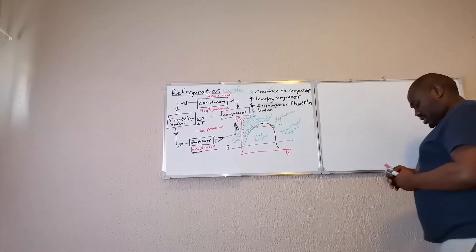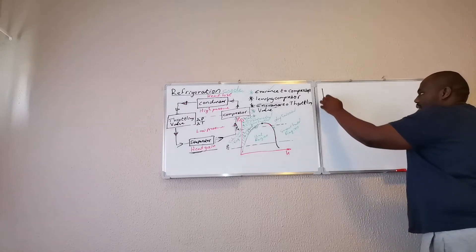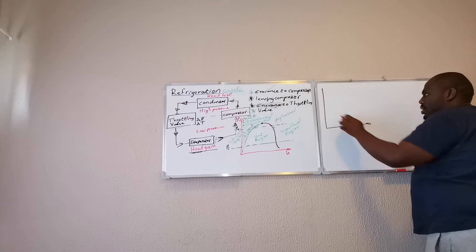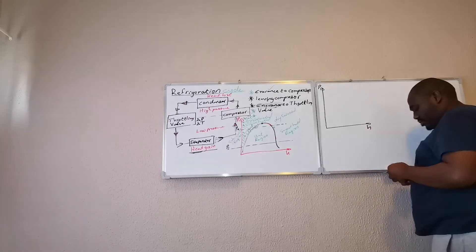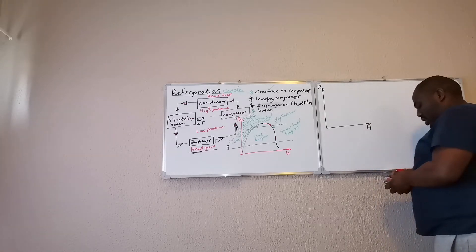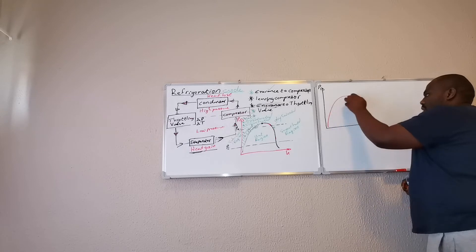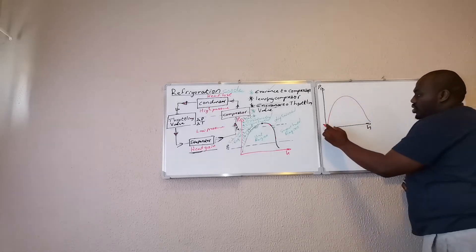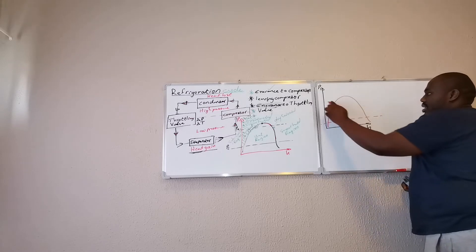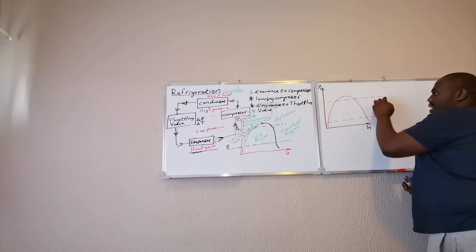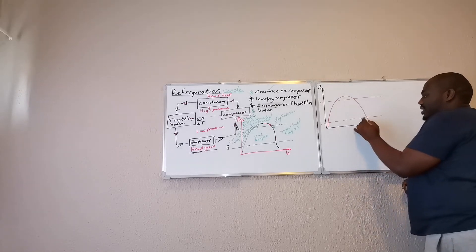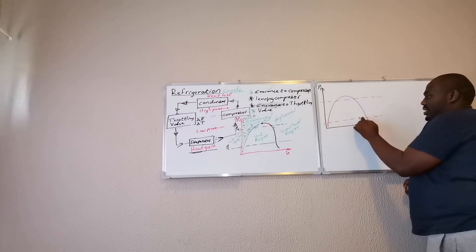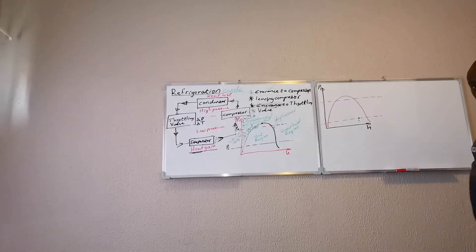Okay, so let's draw this diagram on a pressure versus enthalpy diagram. So, this is your low pressure line, your evaporator line. This is your high pressure line, your condenser line. So, my first assumption is that this refrigerant is entering wet at low pressure. So, my point would be there. Point one would be inside the wet region.